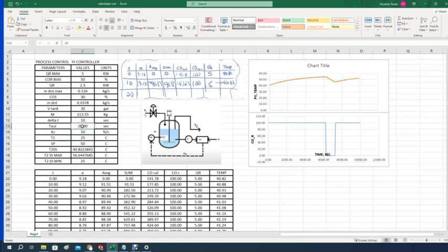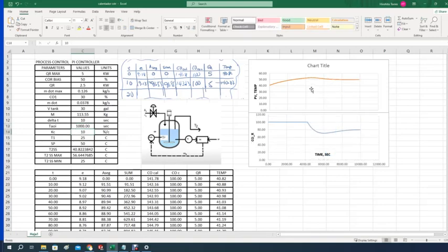So let's go back. The optimum value might be around 1,000 somehow. Let's see, 1,000. But at 1,000, it goes up. I don't like this. Maybe that overshooting is not good. You don't want overshooting, particularly if you are working in pharmaceutical and the temperature has to be limited to 50. You don't want this to happen. So you want to dampen that PV to stay underneath until it hits the 50. So that's really what you want. To do that, then this value might be like 2,000.